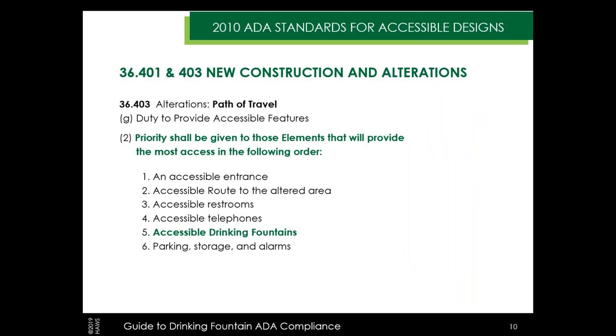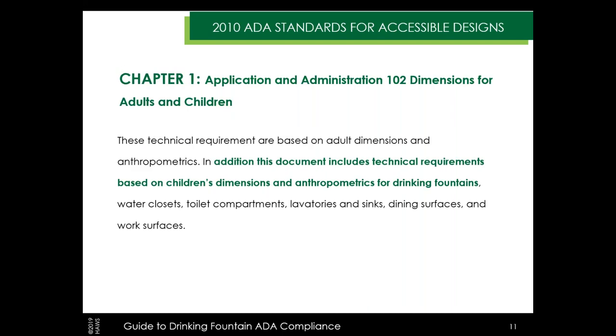Section 36.403 gives us a list of priorities when making alterations to provide accessibility in your facility. Drinking fountains take a pretty high priority — even over accessible parking. The list includes entrance routes, restrooms, public telephones, fountains, parking, storage, and alarms. Chapter 1, Section 102 lets us know that the document contains both adult and children's requirements based on anthropometrics — the measurements and capabilities of the human body. Children are defined as age 12 or younger in the ADA.